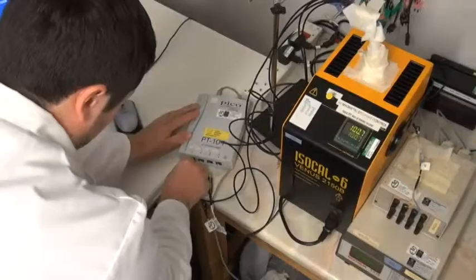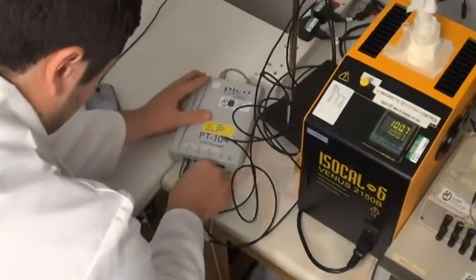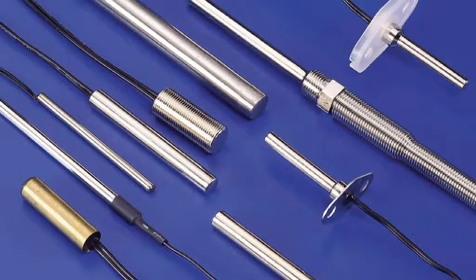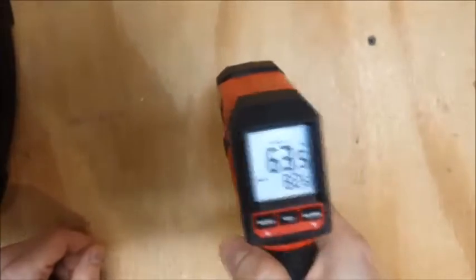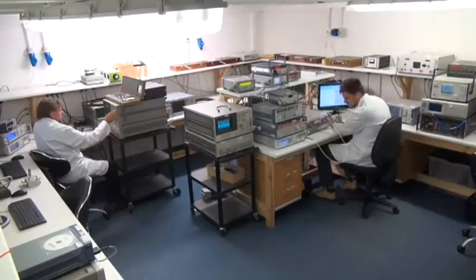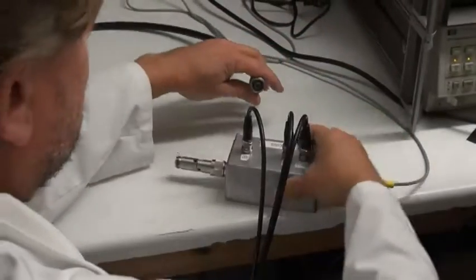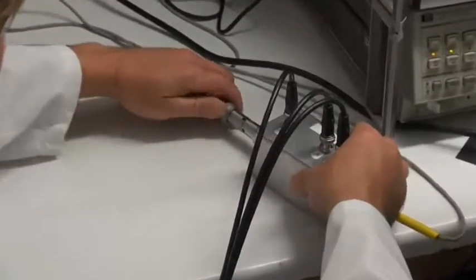We can calibrate temperature measuring devices using our reference thermometer and temperature block including thermocouples, thermistors, PRT and infrared devices. We have our RF standards room which is also temperature and humidity controlled, which ensures precision and consistency with our measurements.